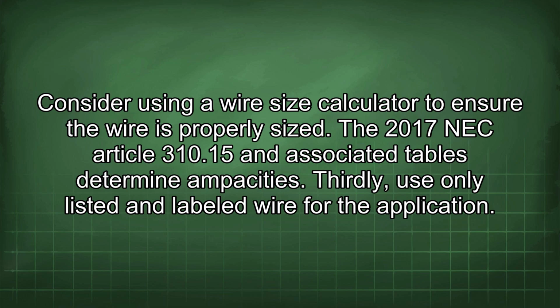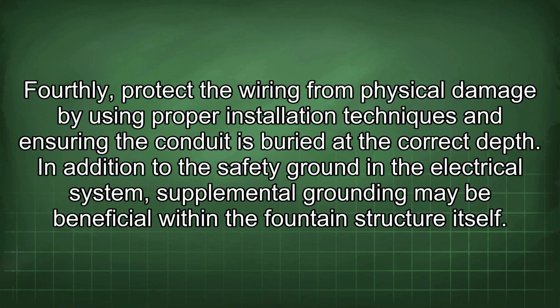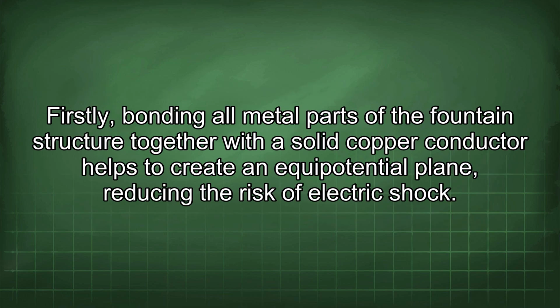Thirdly, use only listed and labeled wire for the application. Fourthly, protect the wiring from physical damage by using proper installation techniques and ensuring the conduit is buried at the correct depth. In addition to the safety ground in the electrical system, supplemental grounding may be beneficial within the fountain structure itself. Firstly, bonding all metal parts of the fountain structure together with a solid copper conductor helps to create an equipotential plane, reducing the risk of electric shock.